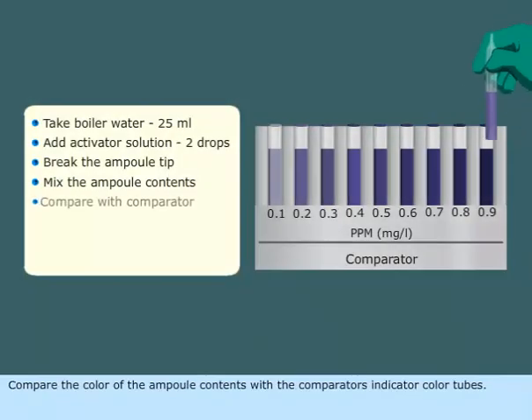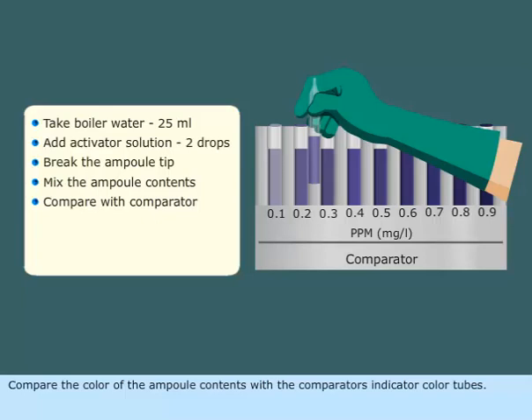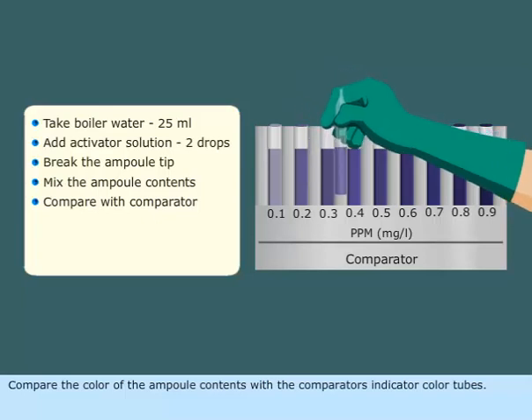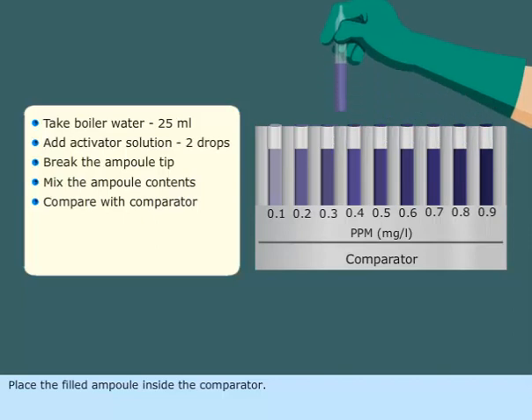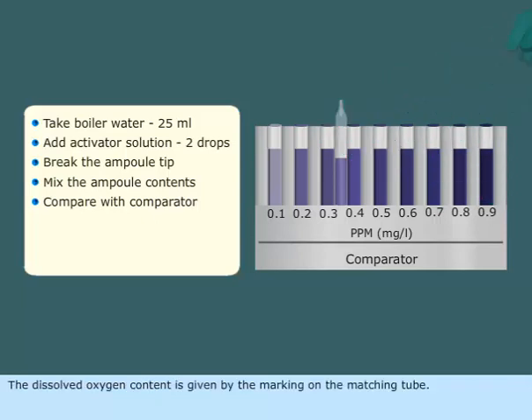Compare the color of the ampoule contents with the comparator's indicator color tubes. Place the filled ampoule inside the comparator. The dissolved oxygen content is given by the marking on the matching tube.